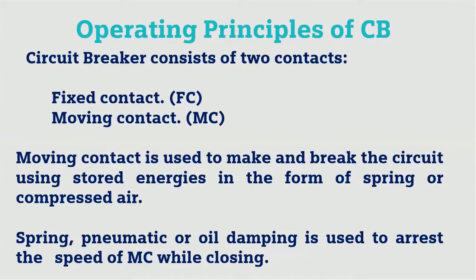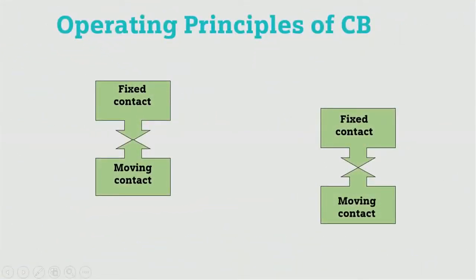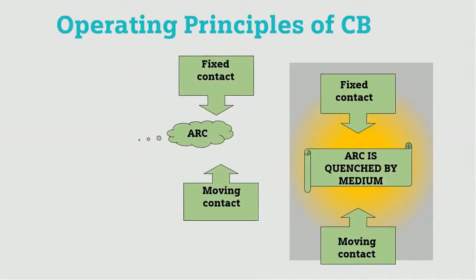The circuit breaker consists of two contacts: fixed contacts and moving contacts. The moving contact is used to make and break the circuit using stored energy in the form of a spring or compressed air. Spring, pneumatic, or oil damping is used to control the speed of the moving contact while closing. When a fault occurs, the circuit breaker breaks the contact and an arc is produced.